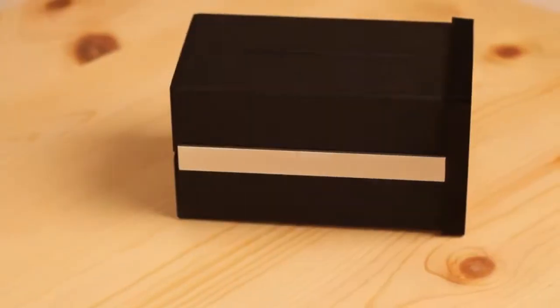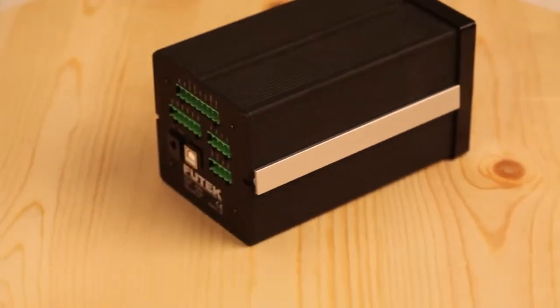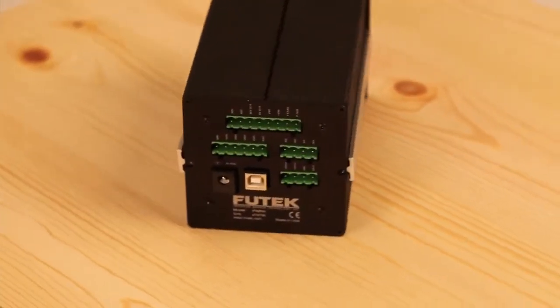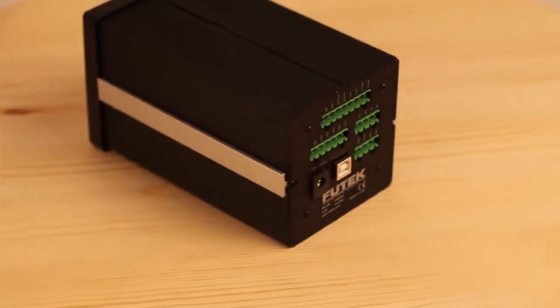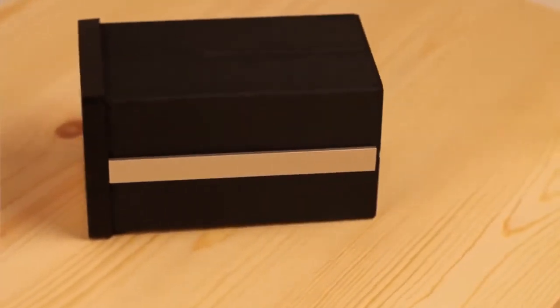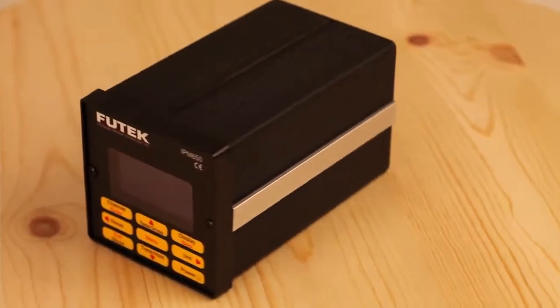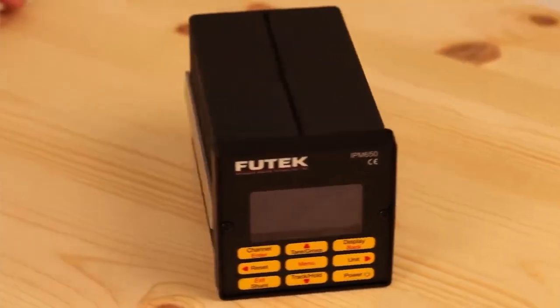Additionally, there are two solid-state relays that can be used in conjunction with the alarm functions in the IPM650. The IPM650 can store 21,000 points of information for a data logging test. There's also a shunt calibration feature, as well as a first peak and valley function. The IPM650 can store up to 14 different sensor channels or calibrations, and it also supports TEDS template 30 and 33.